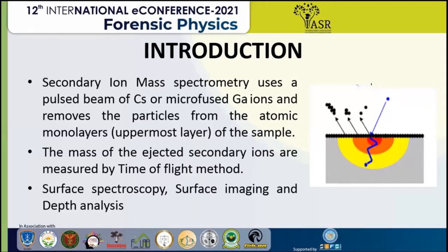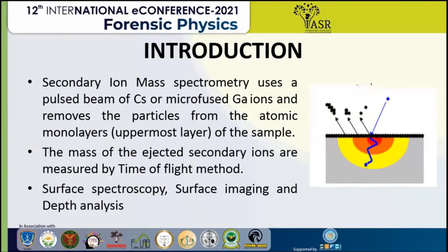In this technique, the instrument uses a pulsed beam of heavy ions, usually micro-focused gallium ions, and removes very minor particles from the uppermost atomic monolayer of the sample. The mass of the secondary ions ejected is measured by the time of flight method — how the time of flight from the detector is measured. This instrument can be used in three operational modes: surface spectroscopy, surface imaging, and depth profiling.